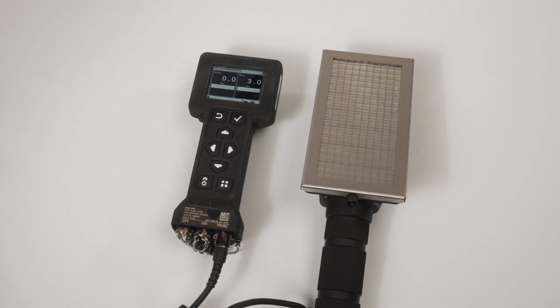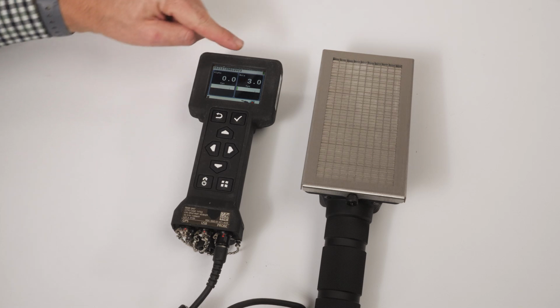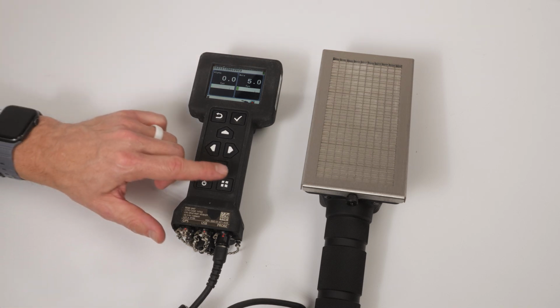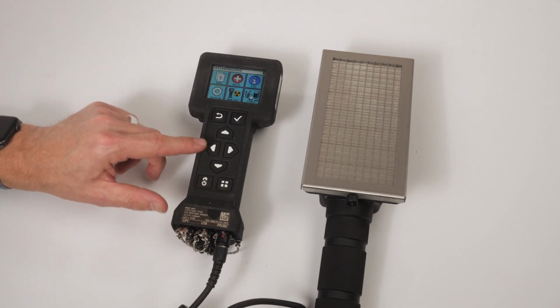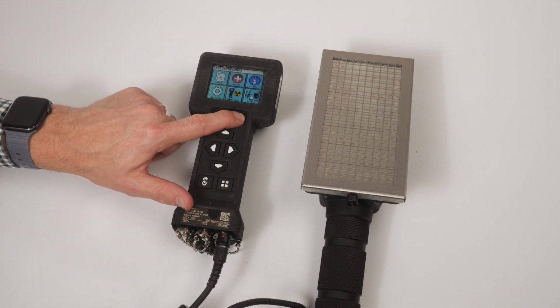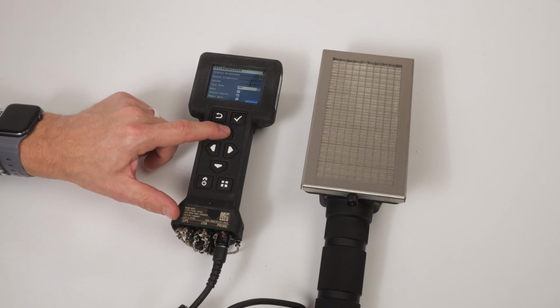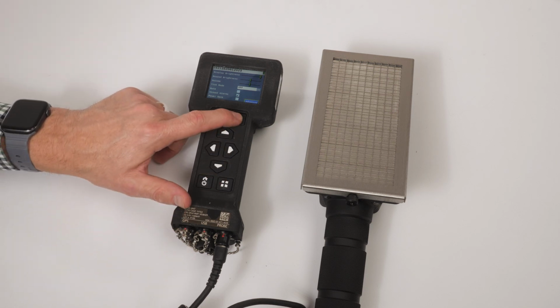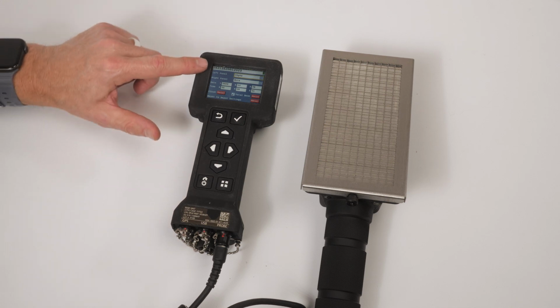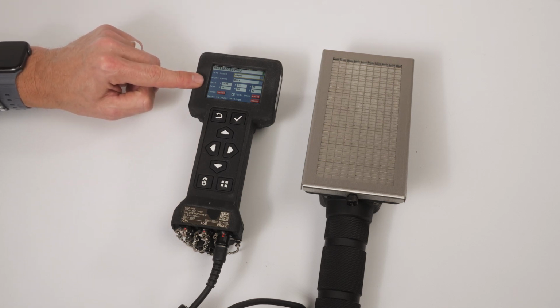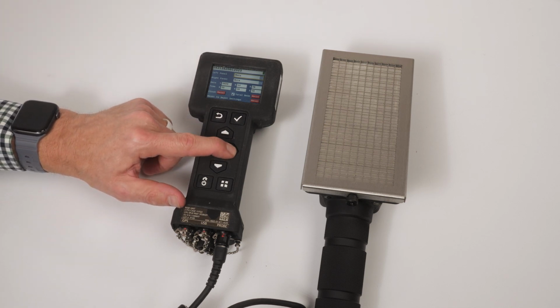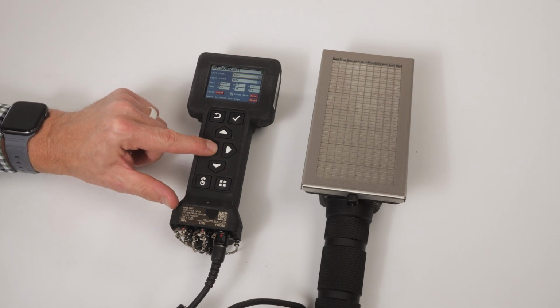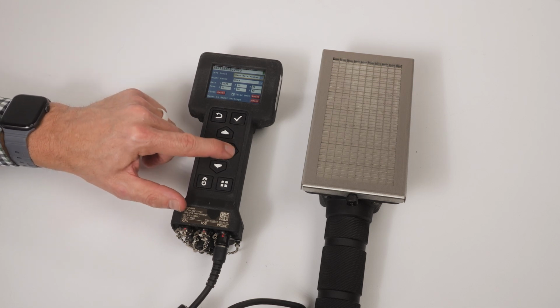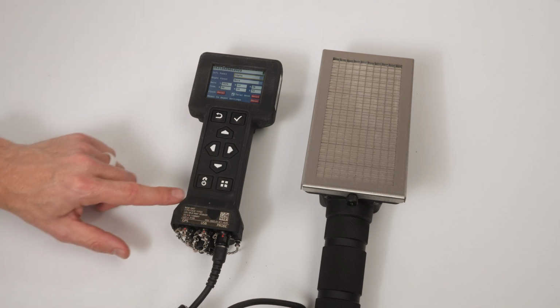We will now cover menu items related to the alpha-beta probe. First, let's go over how to change what radiation readings are displayed in the left and right radiation reading panels of the home screen. Press the menu key, use the arrow keys to highlight settings, then press the enter key to select it. Use the arrow keys to highlight the advanced button and press enter. You can choose what radiation readings to display in the left and right panel on this screen. Use the arrow keys to change panel options. Then press the home key to view the changes made.